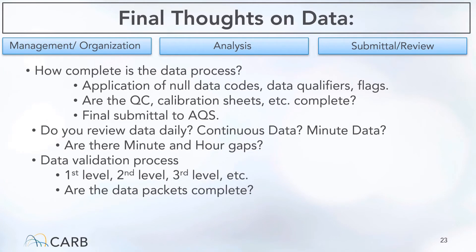To end on data, here are some final thoughts and questions that we want to ask ourselves. How complete is the data process? Is the application of null codes proper? Are the null qualifiers and flags properly coded to tell a story? Are the QC calibration sheets complete? How ready is it for submittal to AQS? As site operators, do we review data daily? How does the continuous data look? Do we look at the minute data as well? Are there any minute gaps or even hourly gaps? For the data validation process, is your first-level, second-level, and third-level data validation complete? How complete are your data packets? Ultimately, the main point is: is our data validation and our documentation complete?